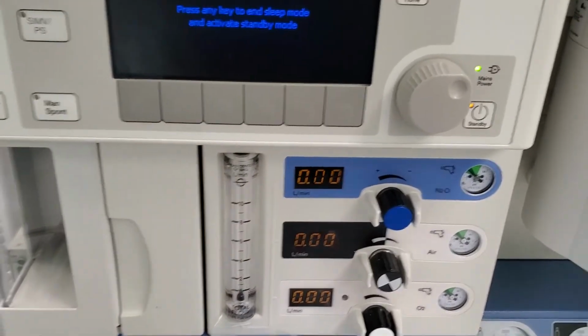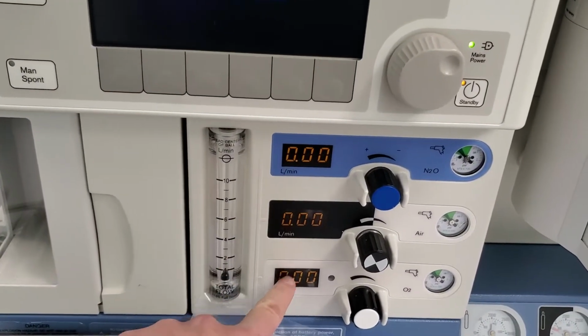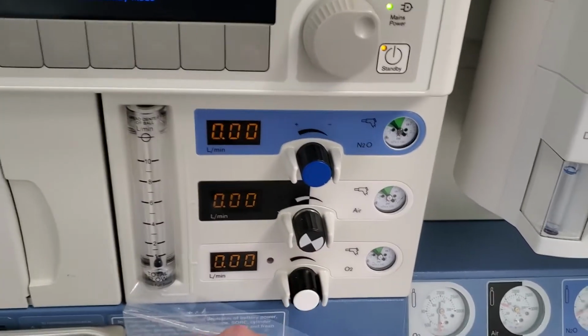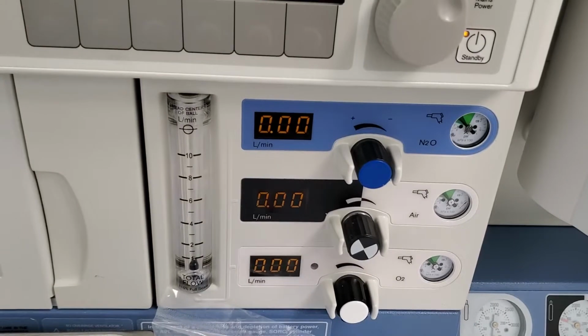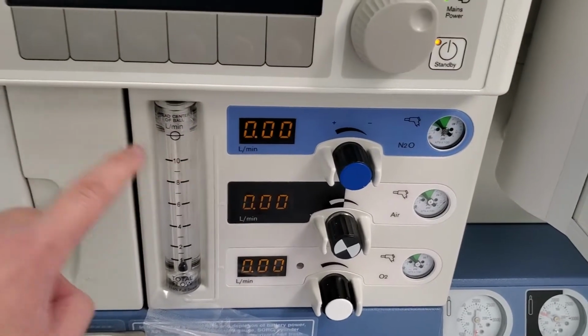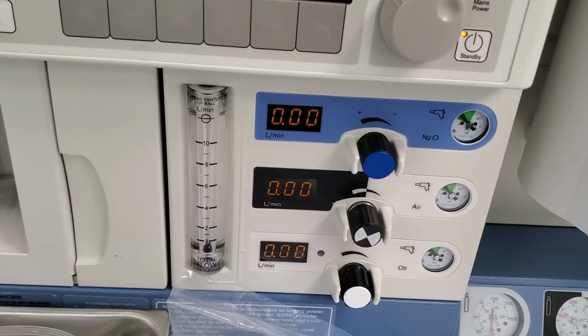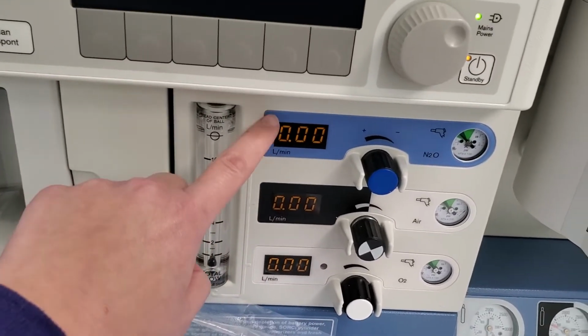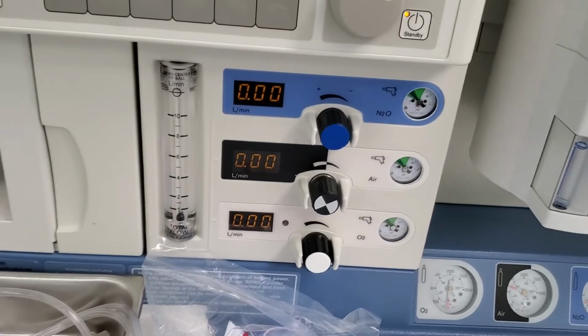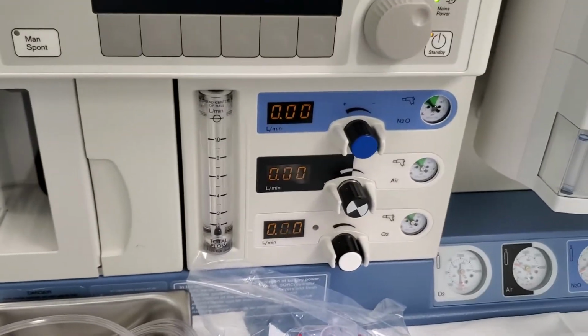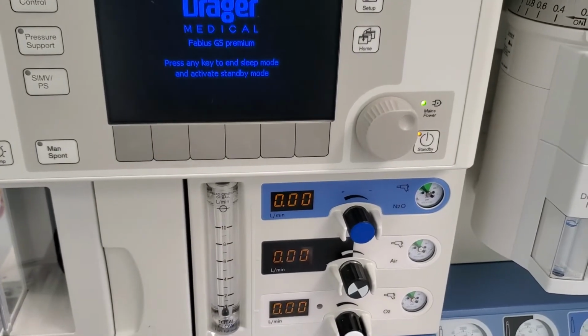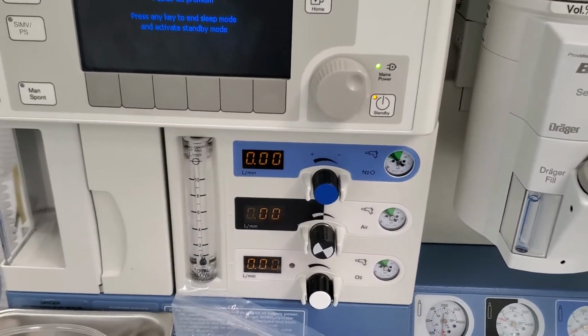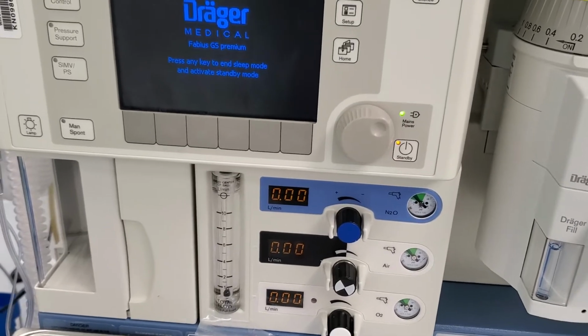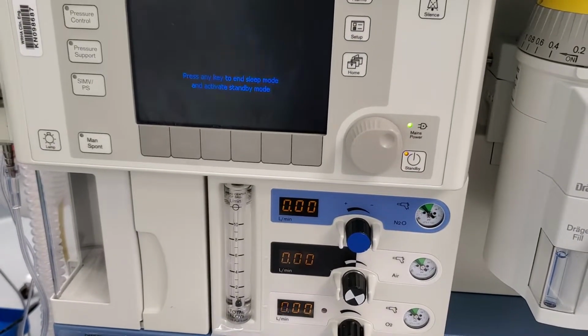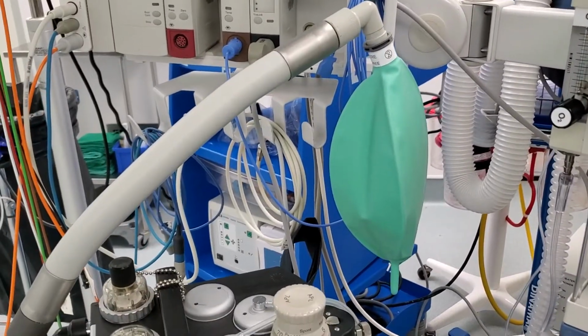We have a total fresh gas flow meter. Because we have digital displays, we can deliver nitrous, air, and oxygen, and it's more accurate than the flow meter. So we just need a total flow meter in case our backup battery died and we didn't have digital displays anymore. If the machine has a power outage, you can still deliver a manual anesthetic, but the backup battery does not have enough power to provide ventilation. So you would just have to close your APL valve a little bit and squeeze the bag.